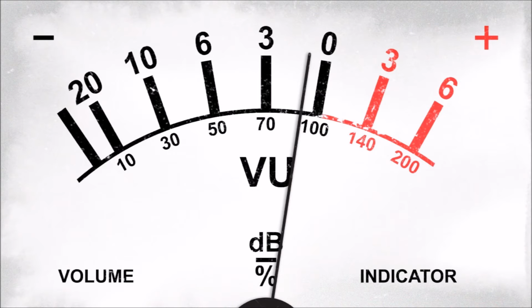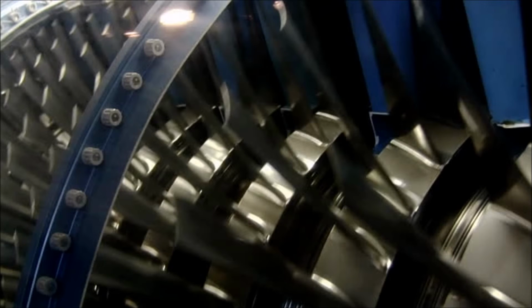Rotodynamic compressors. In rotodynamic compressors, the pressure rise of refrigerant is achieved by imparting kinetic energy to a steadily flowing stream of refrigerant by a rotating mechanical element and then converting it into pressure as the refrigerant flows through a diverging passage. Unlike positive displacement type, the rotodynamic type compressors are steady flow devices, hence are subjected to less wear and vibration. Depending upon the construction, rotodynamic type compressors can be classified into 1.